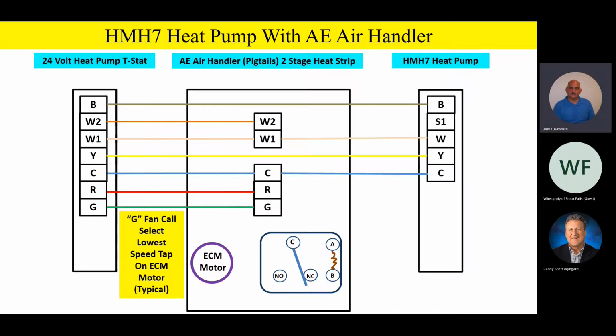G terminal is the 24-volt fan call from the thermostat to G. And what that's going to do is allow us to bring the fan on. Now, please note, if a homeowner goes over to the thermostat subbase assembly and selects just fan on, in other words, it's not calling for heating, it's not calling for cooling, they just want to circulate some air, maybe they've got some indoor air quality products and they just want to keep the air moving, we're going to recommend that G call from the thermostat to the indoor unit is on the lowest speed tap on that ECM motor. And that's just a very typical way to do it.